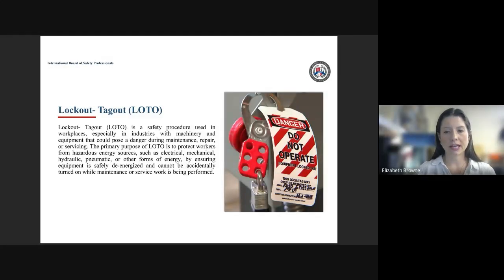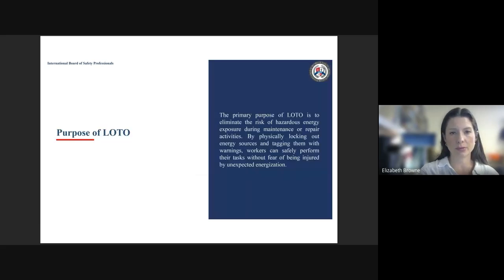All right, so lockout tagout is a safety procedure used in workplaces. Every piece of equipment should have a written lockout tagout procedure that tells step by step an employee how to properly shut down and lock out the equipment so that all hazardous energy sources are controlled. Again, that can be electrical, mechanical, hydraulic, pneumatic, potential energy, gravity. All of those things are considered hazardous energy sources. And so we must safely dissipate any stored energy and de-energize the equipment. And then we're going to apply a lock or some type of device and a lock to make sure that that energy cannot be turned back on while the employees are working on the equipment.